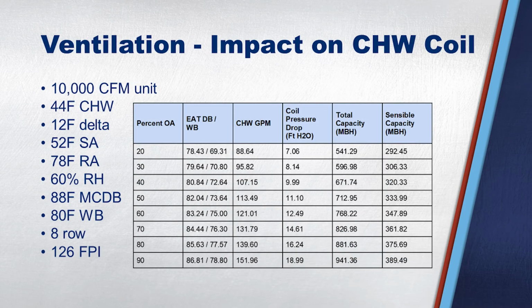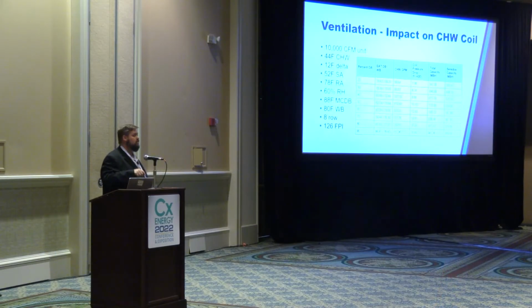Going back to that, can we increase the outdoor air? I thought, yeah, maybe, let's look. So I called a friend and said, hey, can you select a 10,000 CFM unit under worst case conditions in Florida, typical water temperatures, etc., lock in that coil, and start ratcheting up your percent of outside air. What does that do? We found we could get to about 90% outside air and the coil would still be selected per their program.